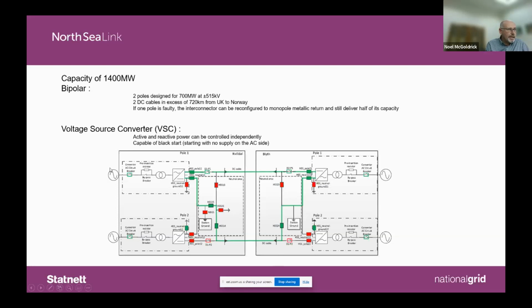What we have is the AC connections, a pre-insertion resistor and an AC breaker, then transformers, then into the converter station, and then the DC side. On the DC side we have switches and disconnectors used to configure from bipole to monopole and back. Looking at the connection, we have just two cables, so in monopole operation we use one cable as a metallic return. Unlike some designs, we don't have a third cable for metallic return; we have one station or system ground, in the UK, which provides a voltage reference for normal operation.